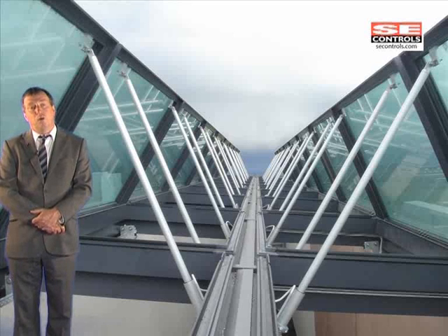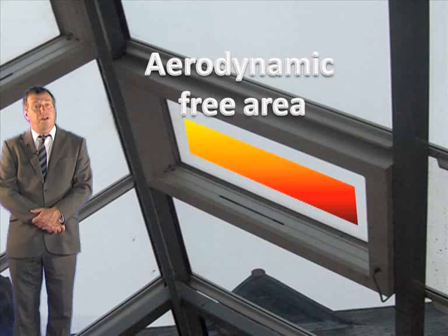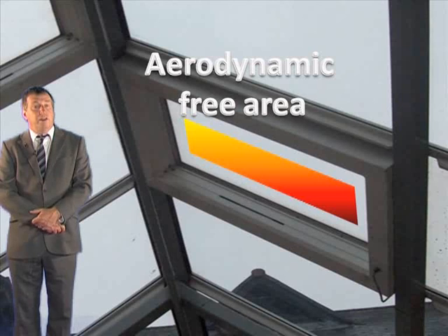Well, we don't always know which precise ventilators are going to be chosen to provide the ventilation, so we don't know what precise CV value they will have. What we can work out is the effective area of ventilation required, that is the aerodynamic free area, and then it is up to the building designer to choose the ventilators that best suit his design needs and that also suit the functional needs of effective smoke exhaust.